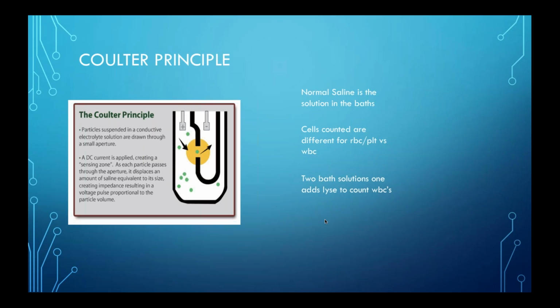Obviously, for the cells to go through this aperture, it uses 6 inches of vacuum on the back side. Where you see the arrows here, the cells go through. If I want to get a little more in depth, they swirl as they go through. As the vacuum goes through, there's also suction from the top, so the cells don't get counted twice. If it stays there and swirls, out of 4 million cells, you might get 100,000 counted twice. So they use a statistical formula based on that number to adjust the average count. But these units are highly accurate, and they're very efficient in the lab.